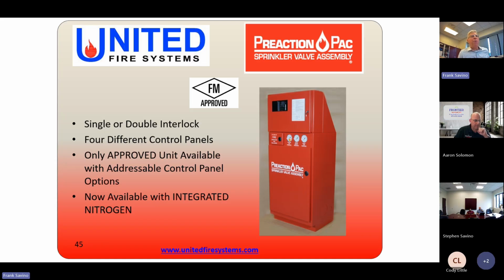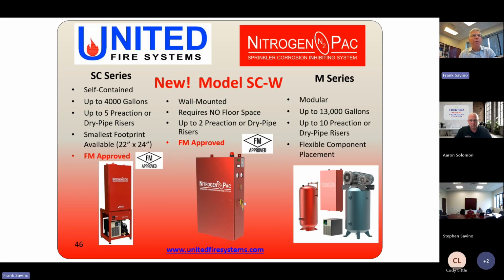In my mind, I would never use anything less than an addressable system for a pre-action system or any system, even a little strip mall. I would use an addressable system. I would never use a conventional fire detection alarm system for many reasons, such as point ID, history buffers, maintenance alert, things like that. So these are other products.